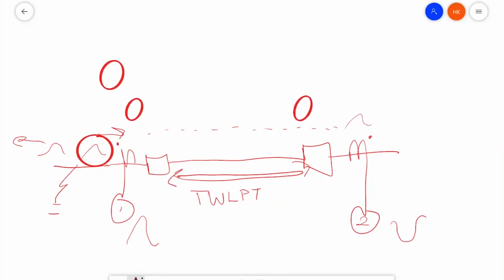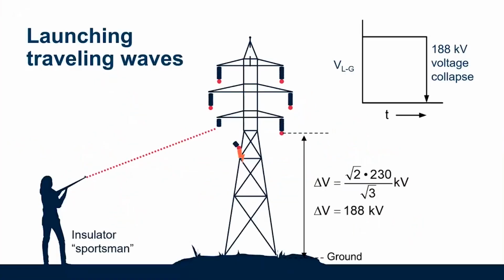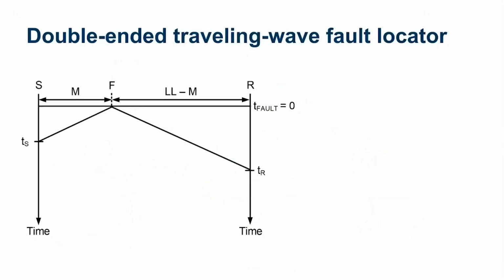All right, so with that said, we can go back to the presentation here, and we can take a look at how the double-ended traveling wave fault locator works. All right, so we have this line going from station S to R. There's a fault somewhere on the line. At this point, the fault is closer to terminal S, so we're going to have a wave launched from the fault point to terminal S.